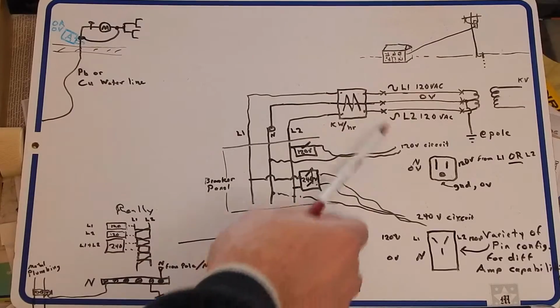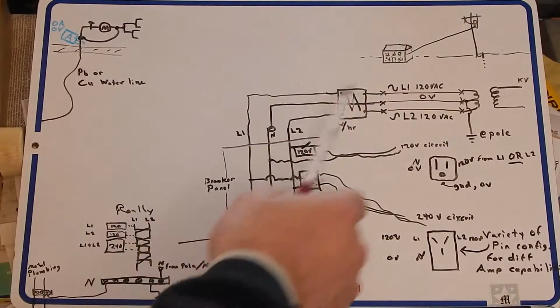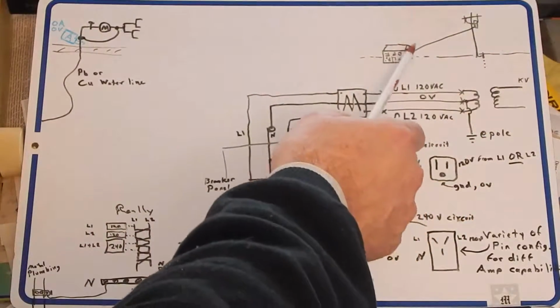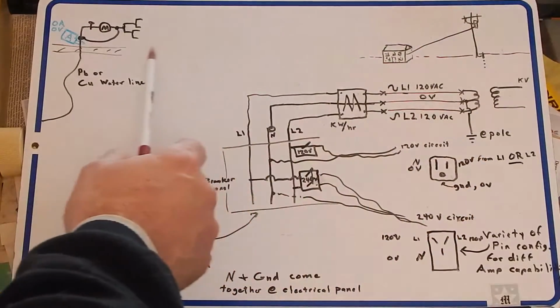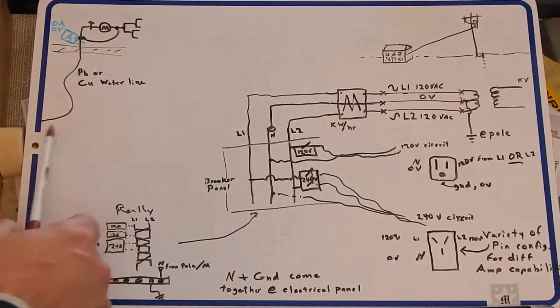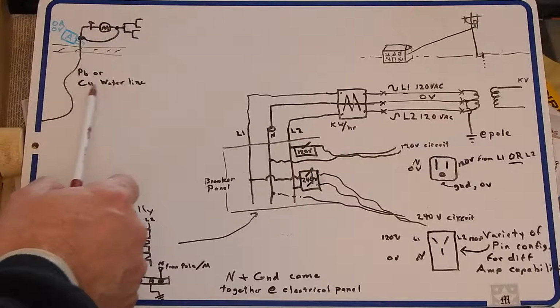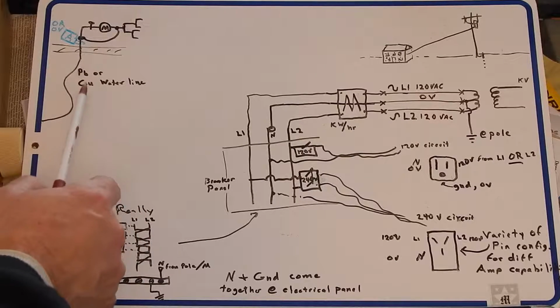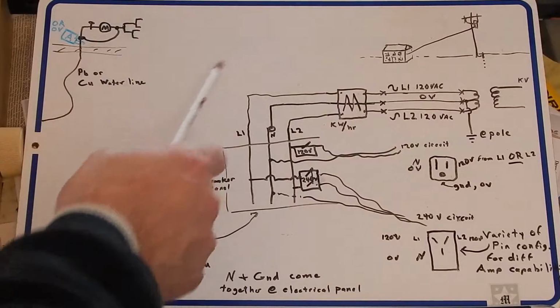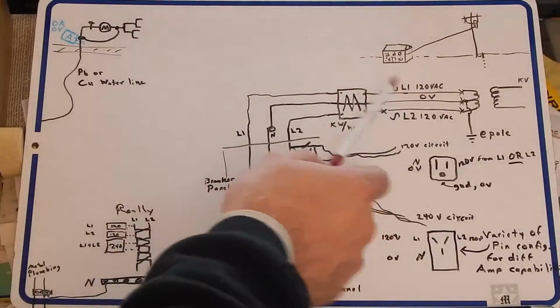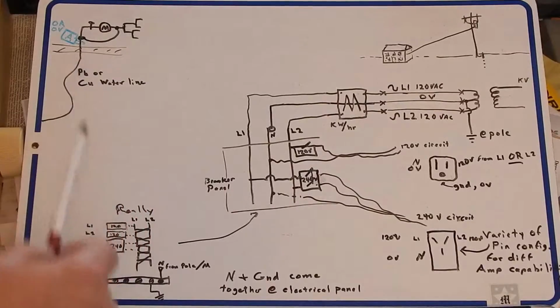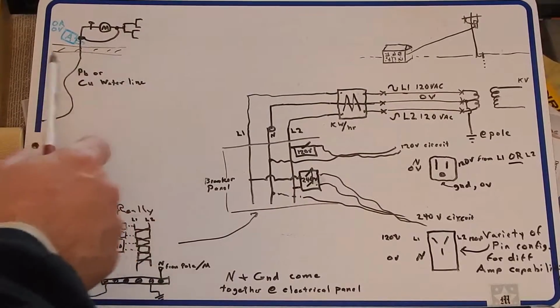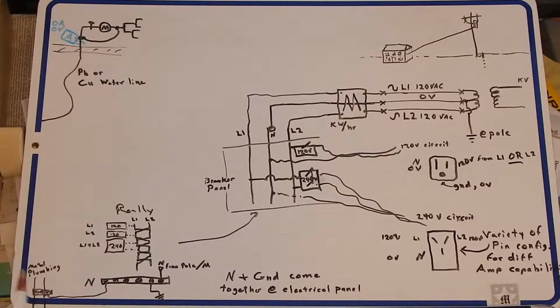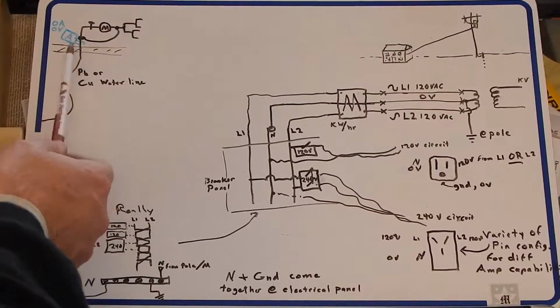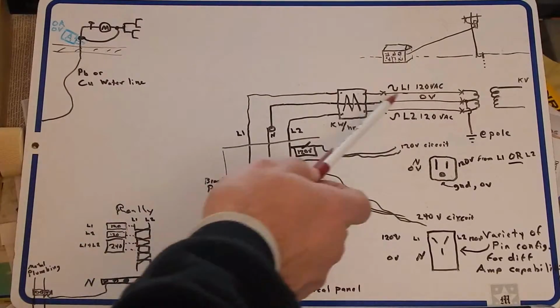Now, if you lose this neutral line, the cable TV wire to the pole, sometimes the phone wire to the pole, or your plumbing, which is usually a copper, or if it's an old house, a lead line coming from the ground. Well, if the neutral breaks, this line is going to take the brunt of the current. That's why they want that jumper across to keep the meter from overheating and burning up and dropping too much voltage as well. But this is not where you want your neutral current to be flowing. You want it to be flowing through this wire.